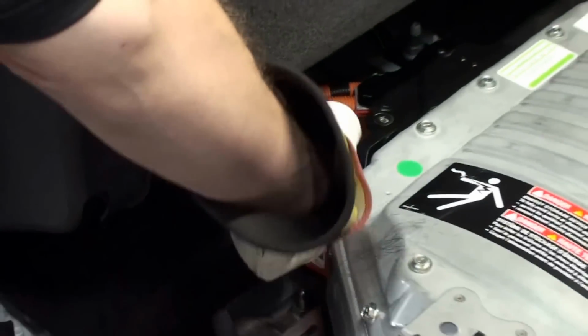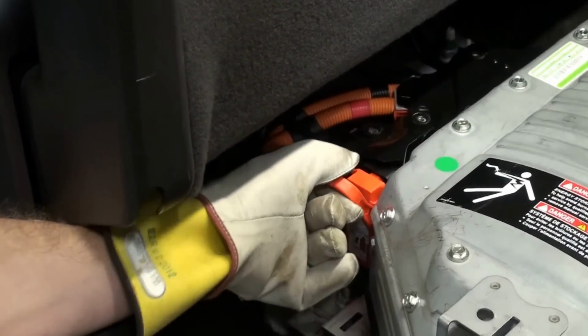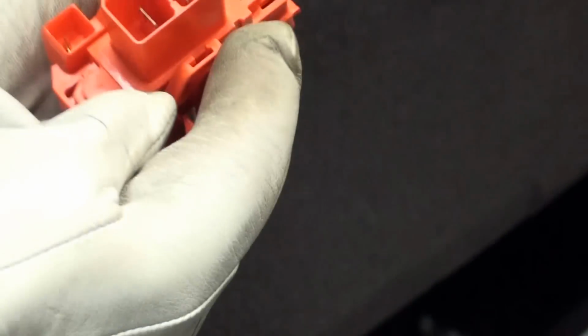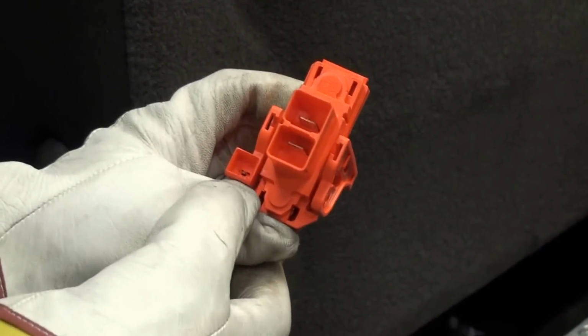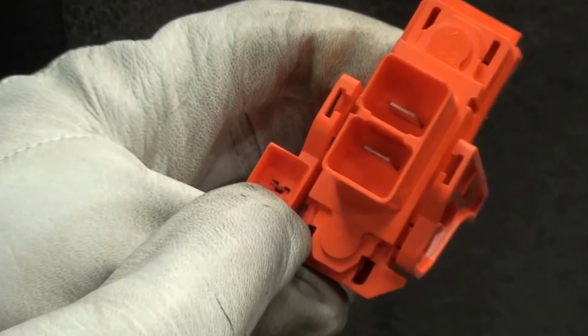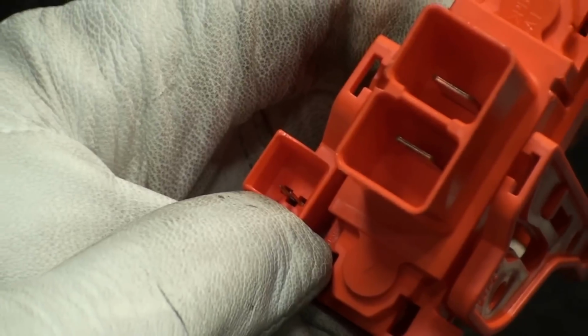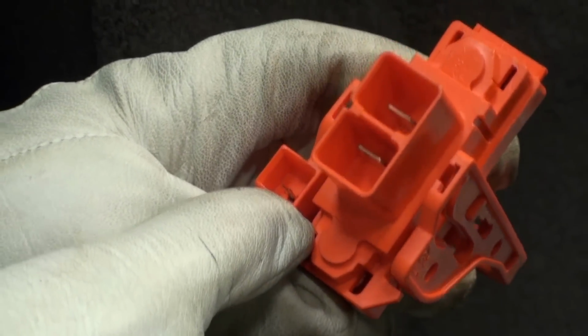We'll put our high voltage gloves on to do the battery pack disconnect, and we'll start with the interlock on the master disconnect switch. We have to lift the bail up and rotate it down to disengage the system. On this one we have small conductors on the left hand side as you look at the connector — those are the interlock circuit for the safety interlock on the high voltage system.